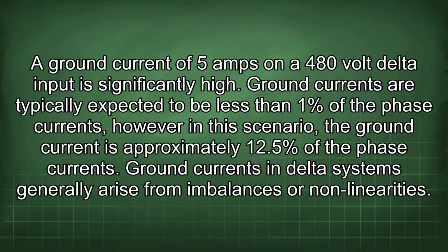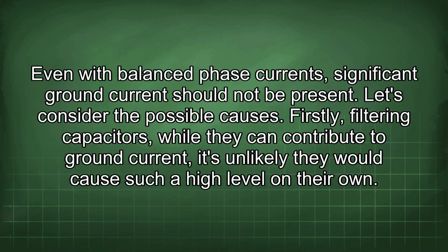A ground current of 5 amps on a 480 volt delta input is significantly high. Ground currents are typically expected to be less than 1% of the phase currents. However, in this scenario, the ground current is approximately 12.5% of the phase currents. Ground currents in delta systems generally arise from imbalances or nonlinearities. Even with balanced phase currents, significant ground current should not be present.